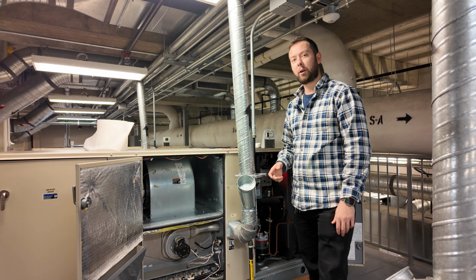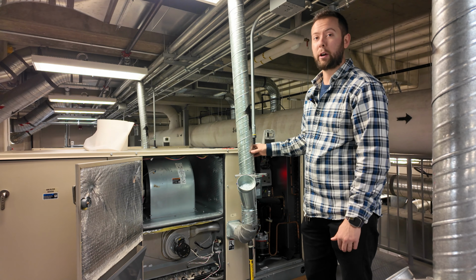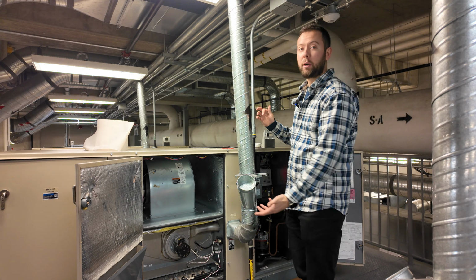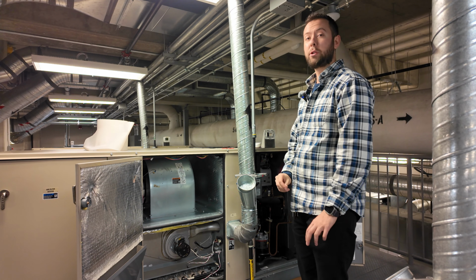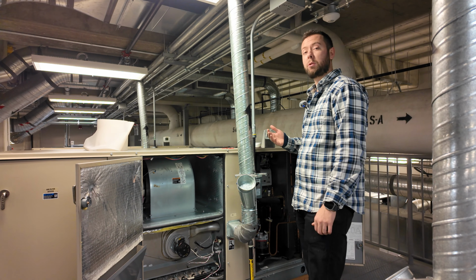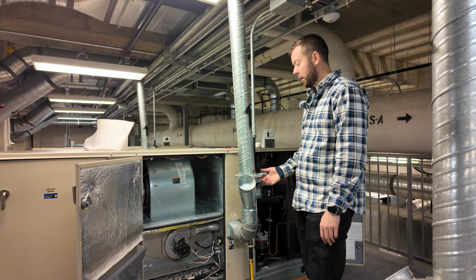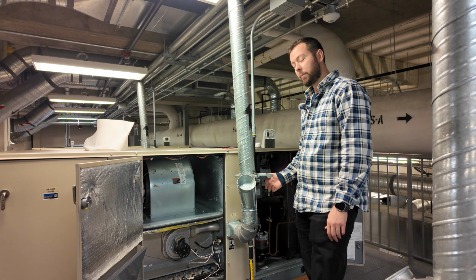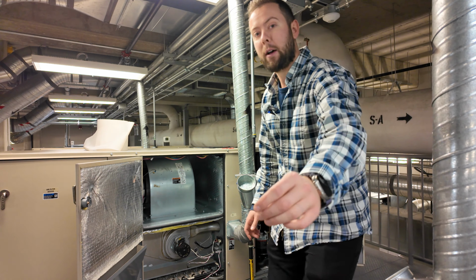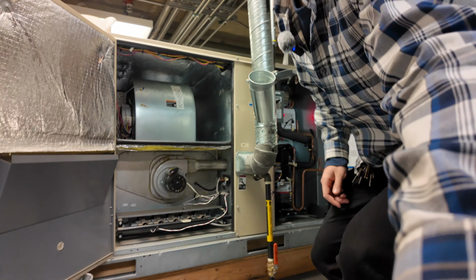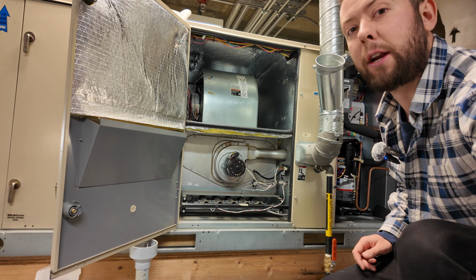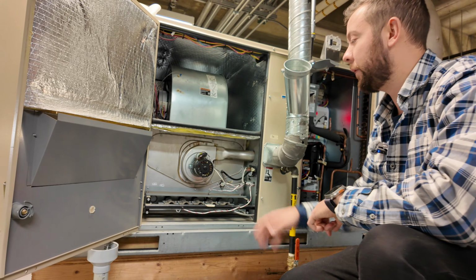When we turn them on here, we have to close the vent as our ventilation's in a negative pressure, and actually we'll close the pressure switch before the combustion motor turns on. We'll get an alarm. So once it starts up, then I usually open it. You'll notice here now the combustion motor has started up, and this is our first step.